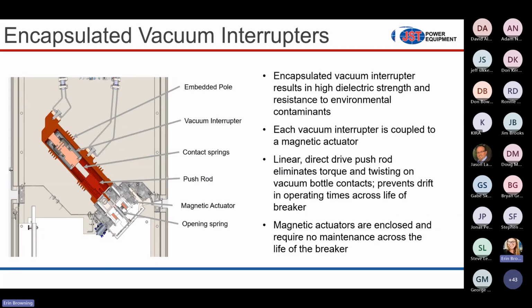So to get into a little bit more of the design of the breaker, I wanted to put this slide on here because this is basically a cross section of the circuit breaker module. The module is the embedded pole, which is the red part. The embedded pole has the vacuum bottle, which is responsible for interrupting current. And then attached to the bottom of the pole is the magnetic actuator, and this is known as the tray. So together, this embedded pole and the tray with the actuators, they make up the circuit breaker module.